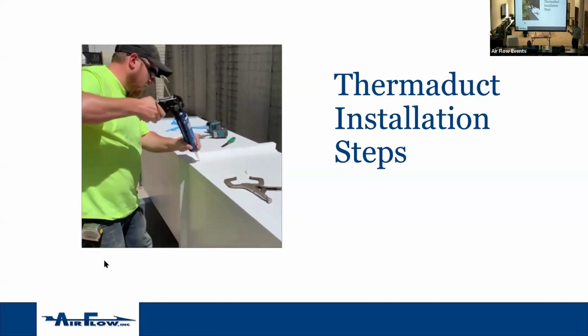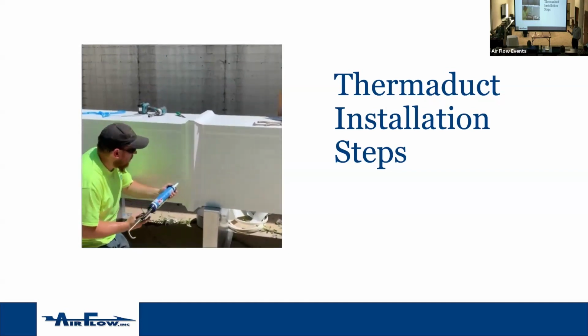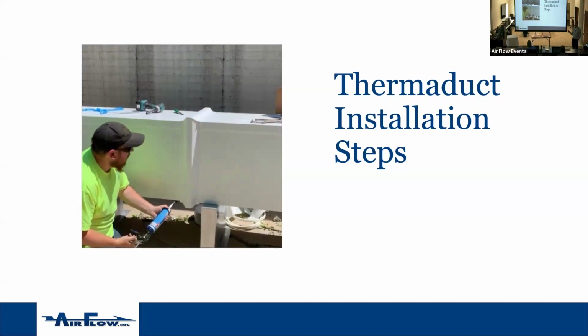And now he's got to caulk, it's basically glue and caulk around that cover. So this is probably the worst part of the job. We have a little sticky tape that goes on both sides. You put it over that gasketing and then you caulk it to hold it, because that little sticky tape isn't going to hold forever. Then it gets sealed up and they take a rag and push that insulation all the way into the corner. It should be faster in the field than conventional sheet metal, and of course, you're done. There's no insulation that's going to come out, there's no clatter that's going to come out, job done.